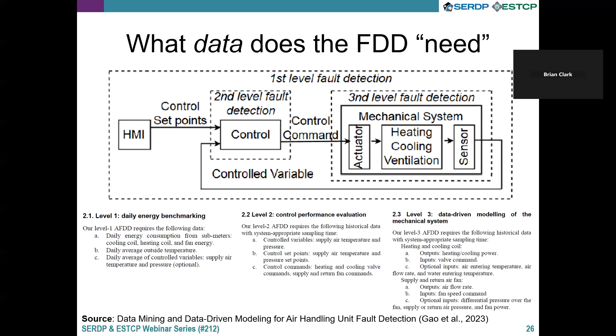Functionality. So another metric, and probably one of the most crucial ones when you're trying to procure, is what do you want the system to do, or rather, what do you want the FDD to know? So this equation up top here is something that I wrote up to try to illustrate what something like an ASHRAE guideline 36 AFDD algorithm looks like, or fault condition. So like I said, there's different levels of sophistication. This is kind of a starting place that we can do something like, instead of look at a supply air temperature and say, is it meeting set point or not, like we would typically do with our alarms, there's a way to get slightly more elegance where you're looking over time.